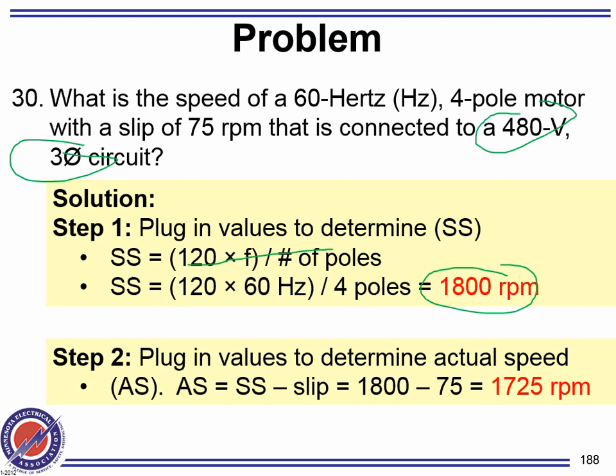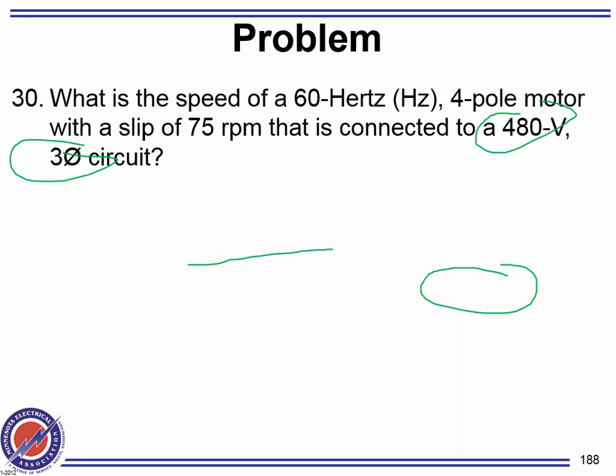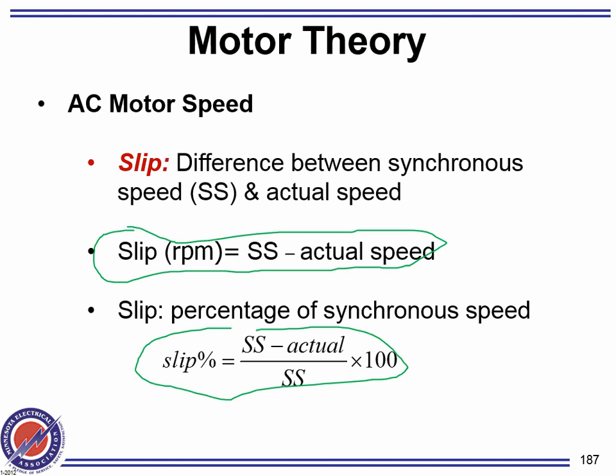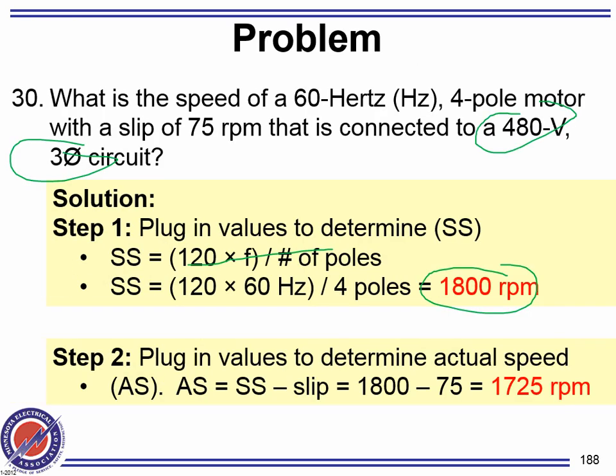Okay, what do you need to know? You need to know how to find the synchronous speed, and the slip is the synchronous minus the actual. Now the slip percentage: 1800, right? So if you need the slip percentage, you take the slip divided by the synchronous speed. So if you take this 75, 75 divided by 1800 RPM, that'll get you the slip percentage.